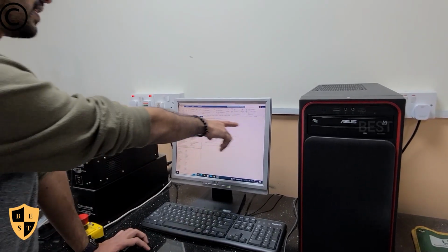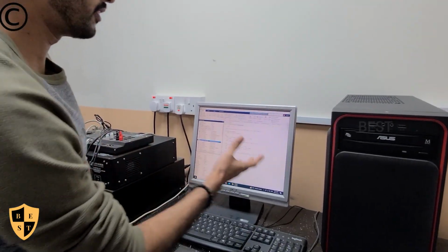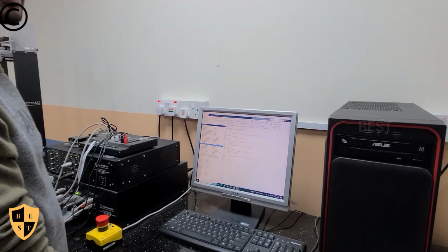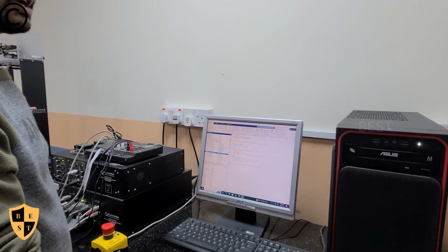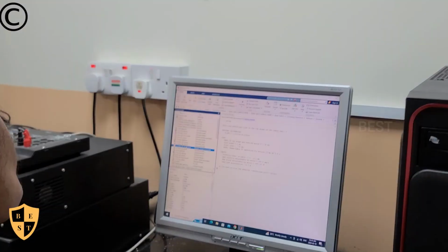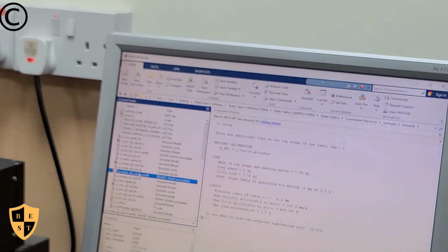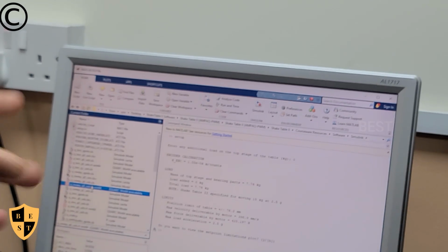So if you need to calibrate the table, we can, if there is a significant mass. This is something we can work with for research purposes. If you are mounting a mass, say 2 kg or 3 kg over the table, we can adjust accordingly, and the response will also be likewise. Because if we are not giving it, the input and the measured table responses will not be the same. Right now it is overlapping, no? If you are not adjusting this, variation will be there. That we don't want.